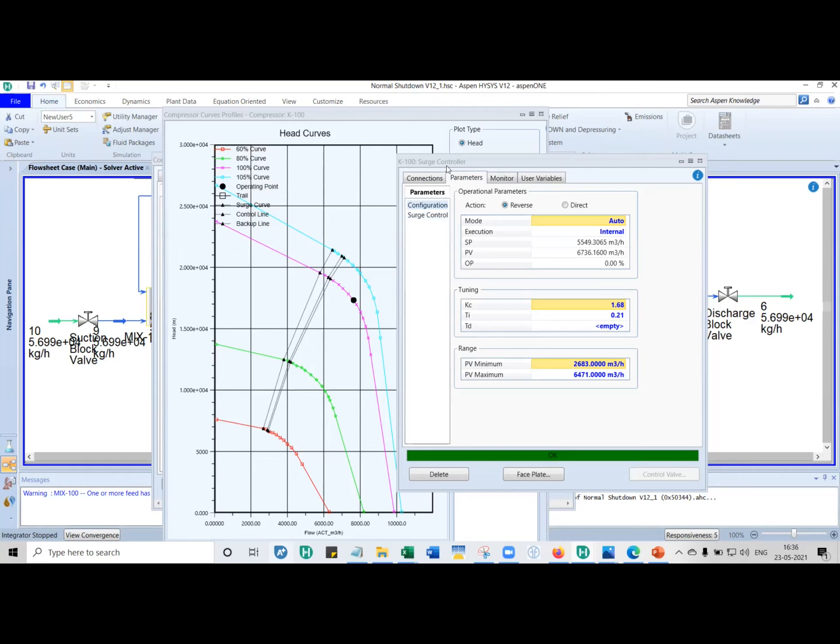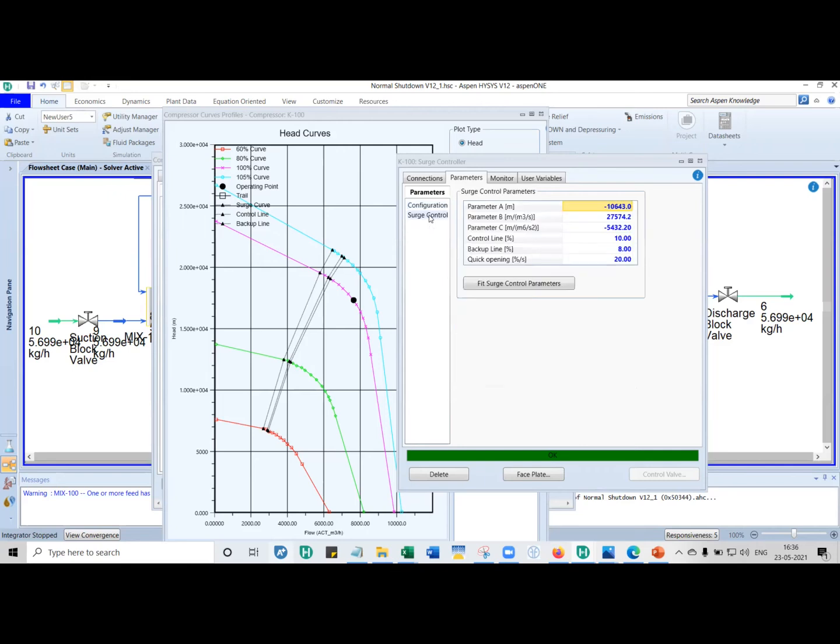But if you're doing a proposal or you're trying to do a simulation to check if a hot gas bypass is required, let's say your junior engineer comes to you and says, do we need a hot gas bypass or not? Because I'm making the preliminary P&IDs, should I put a note, hot gas required and it should recirculate so much percentage of the surge flow? Should I put it or not? Then you can do a simulation like this and decide whether it is required or not. So it depends on the situation, but the final prerogative is with the manufacturer.